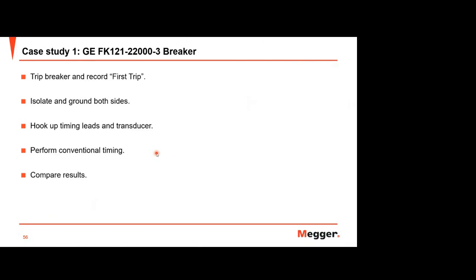So these breakers don't operate for a longer time, maybe one year. And then we try to test it. We try to capture the breaker record for first trip, isolate and ground both sides, hook up timing, and also perform conventional timing after that, and try to compare the results between first trip and the conventional testing method.